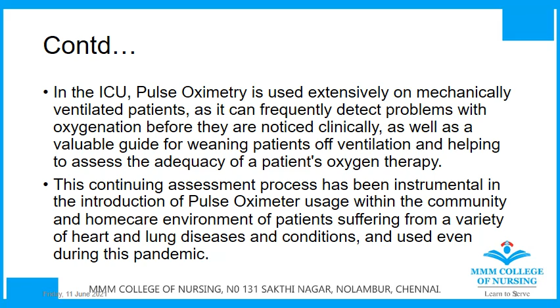So how does this work? The measurements are obtained by simply shining two wavelengths of light at the fingertip. One is a visible red beam and the other one is an invisible infrared beam. By measuring the light that has been absorbed by the oxygen in the blood, an oxygen saturation reading is established, and it is displayed as a percentage of the maximum amount of oxygen in the blood.